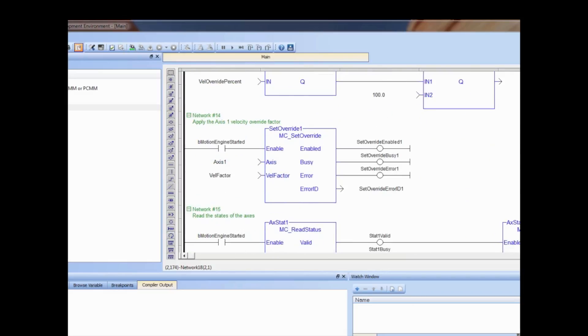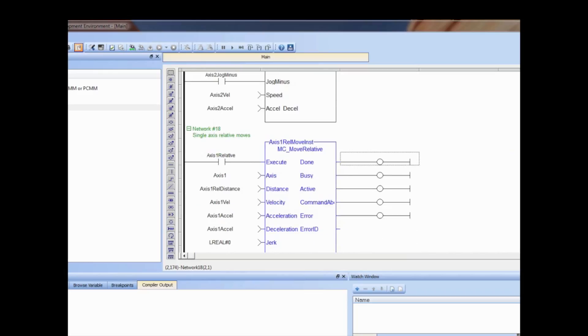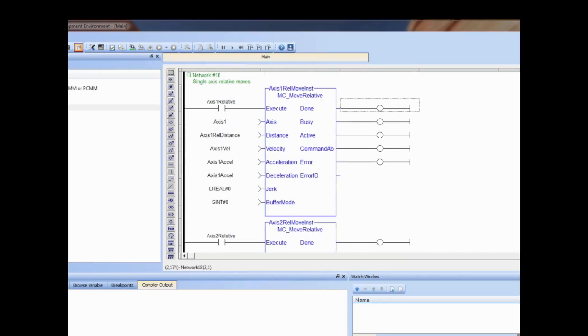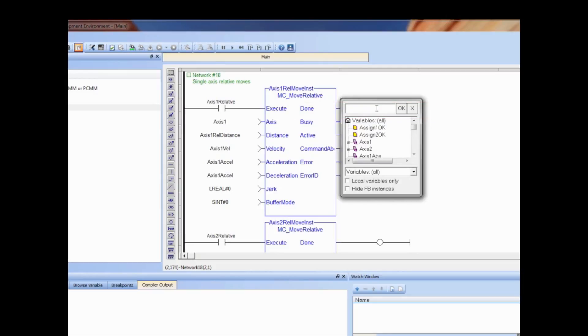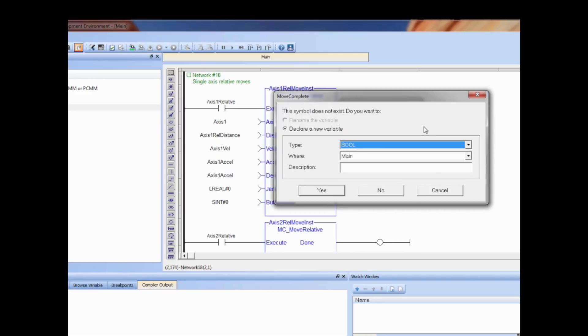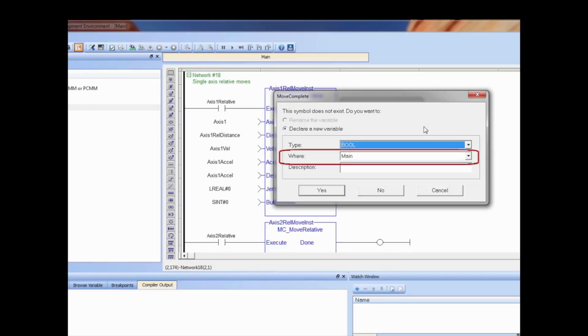I will scroll down to one of the program's relative moves and create a new variable 'move complete' to indicate the state of the relative move function block's done output. Double-clicking on the output coil opens a dialog box to create the variable or select an existing one already defined in the dictionary. In FFLD, the entry box already selects the required variable type.